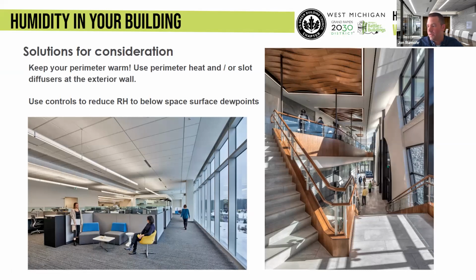These are examples of a couple of projects we've done recently that are highly humidified environments. The graphic on the right is a performing arts facility. In performing arts spaces, you want to keep vocal cords hydrated and instruments and pianos hydrated and in tune. This facility is in northern Michigan, an extremely cold climate, wanting to keep that space at 50% relative humidity all year round, including when it's -5 or -10 degrees outside.